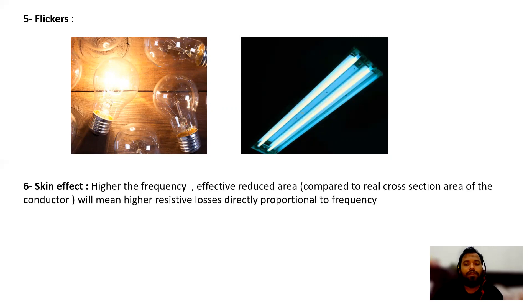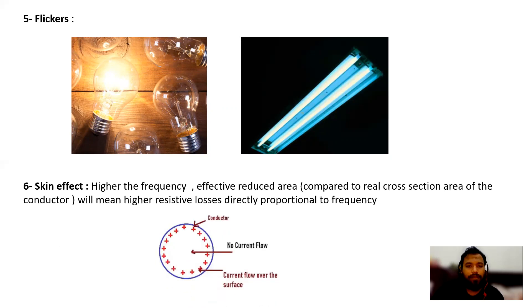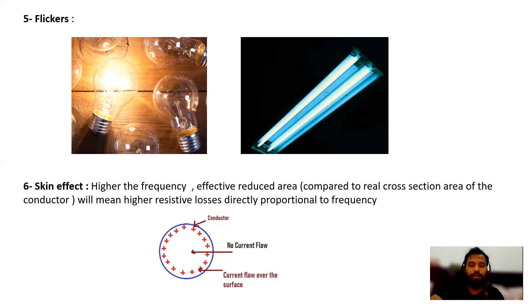The next effect is the skin effect. At higher frequencies the effective cross-sectional area of a conductor is reduced — current only flows on the outer surface of the conductor. Due to this, the maximum conductor utilization is reduced. This skin effect occurs because of higher frequencies caused by harmonics.